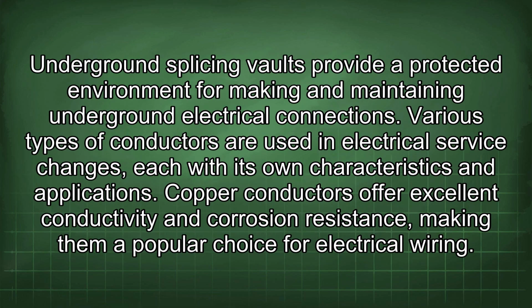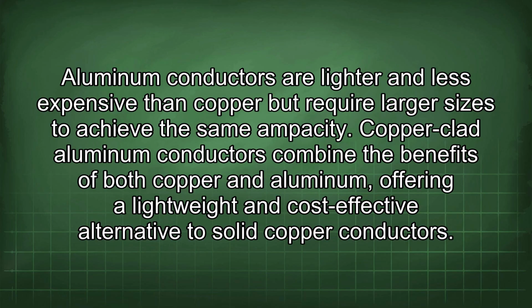Underground splicing vaults provide a protected environment for making and maintaining underground electrical connections. Various types of conductors are used in electrical service changes, each with its own characteristics and applications. Copper conductors offer excellent conductivity and corrosion resistance, making them a popular choice for electrical wiring. Aluminum conductors are lighter and less expensive than copper but require larger sizes to achieve the same ampacity. Copper-clad aluminum conductors combine the benefits of both copper and aluminum, offering a lightweight and cost-effective alternative to solid copper conductors.